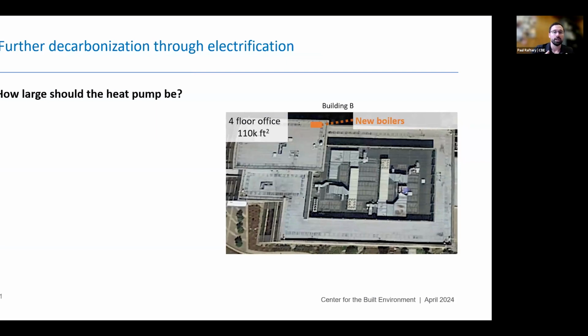So if we were to reduce emissions even further in these buildings, we'd need to switch fuel sources to something cleaner, electric power from the grid. When you look at these sorts of studies, trying to electrify heating, you always have a decision about how large the heat pump or heating equipment should be to offset that boiler capacity. I wanted to step through some of those issues here because that really is a key consideration, and there are some real world practical constraints that sometimes are quite challenging in existing buildings.